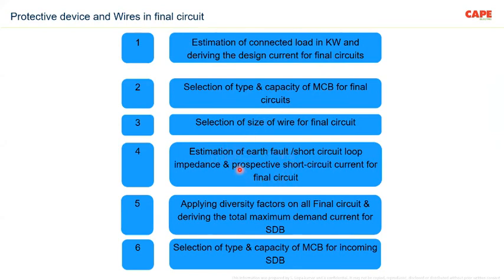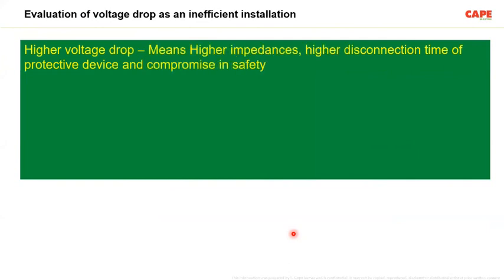Then you also should consider estimation of earth fault and short circuit loop impedance and the prospective short circuit currents, because your device is supposed to trip in case of a trouble. Then apply the diversity factor on the final DBs and select the rating of the incoming circuit breaker, where you can apply the demand factor and diversity factor. These are the steps you are supposed to follow. Why I showed this is that most of the time oversized devices are used, which is also one of the reasons for non-disconnection of the supply, resulting in accidents.